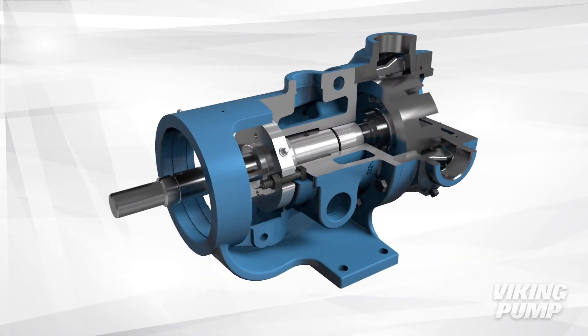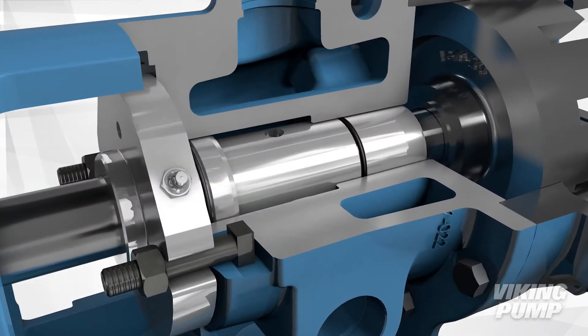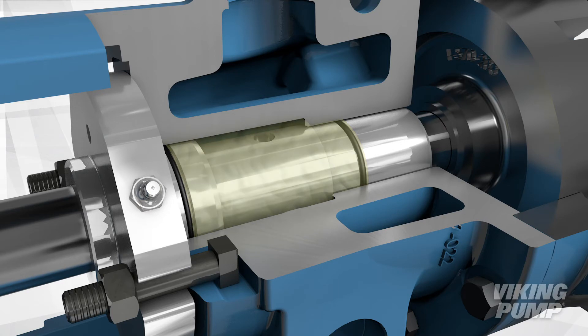Lubricant or grease is injected into the bracket through a grease fitting on the seal gland. This grease fills the bracket, which then enters the space between the O-Pro Barrier Seal and the shaft through an access hole, ensuring smooth operation.